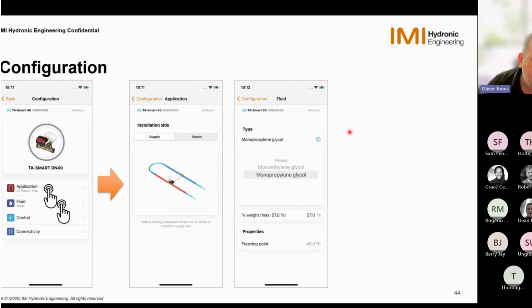If we click fluid, we can then change our fluid from water to monoethylene or monopropylene glycol. We can change the percentage that's in the system, and also the freezing point if need be. And to be honest, I think that's grayed out based on a calculation from what you've selected and the weight of ethylene or glycol that you actually put into the system.